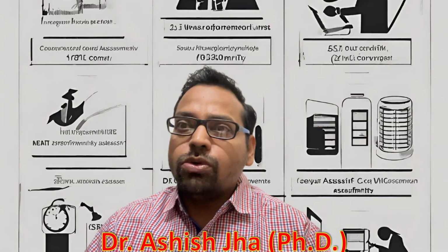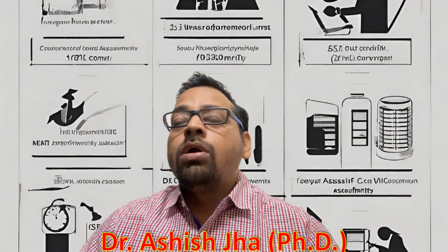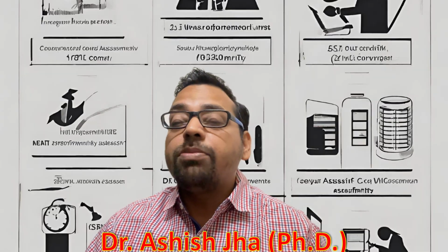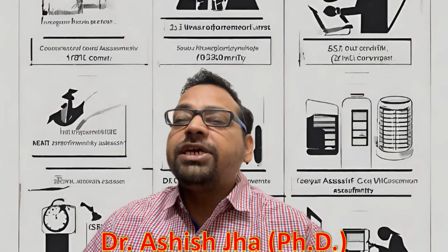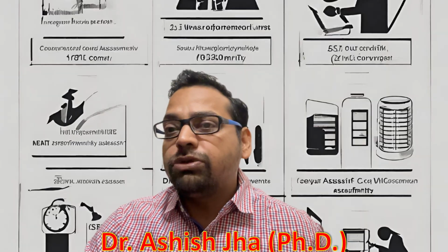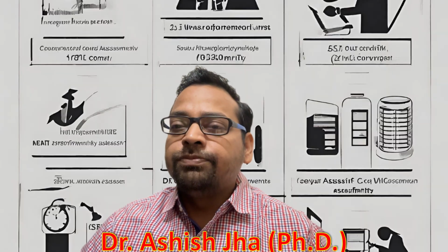So we just need to follow the standards we have, the ISO standards according to the type of medical device and its intended use. We need to follow those particular standards, and then apply. So in essence, in summarized form, a conformity assessment is a process to evaluate each and every piece of data related to the medical device, submitted by the manufacturer to the regulatory authorizing body, and they assess whether everything is in proper shape and as per rules and regulations.